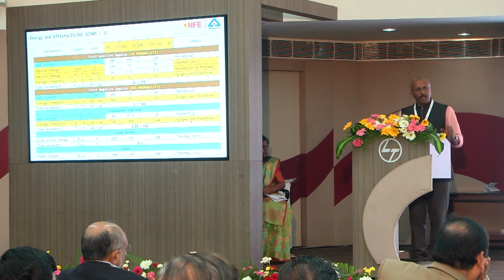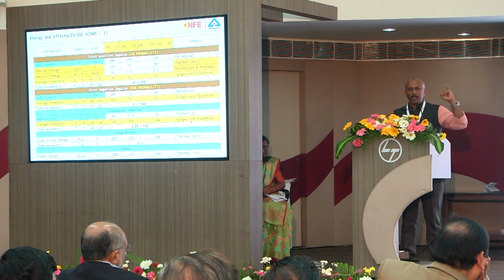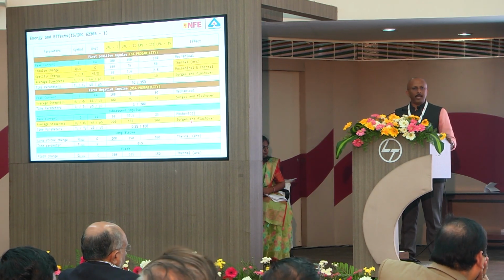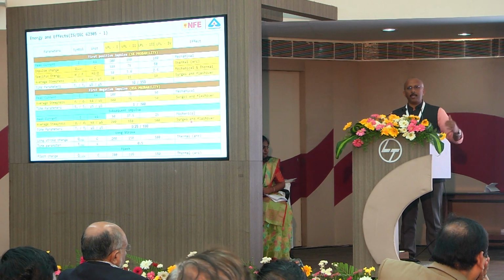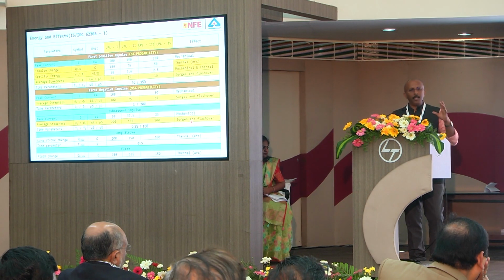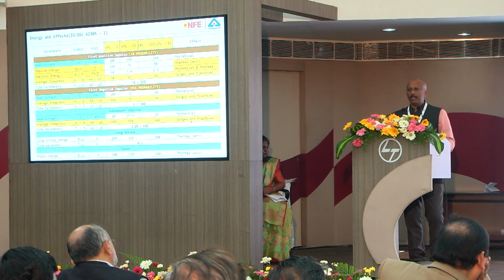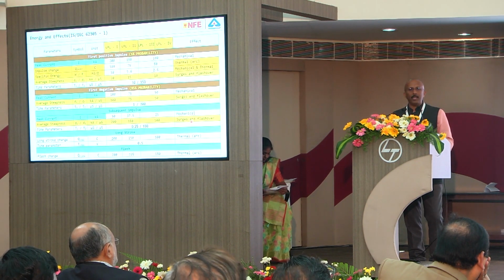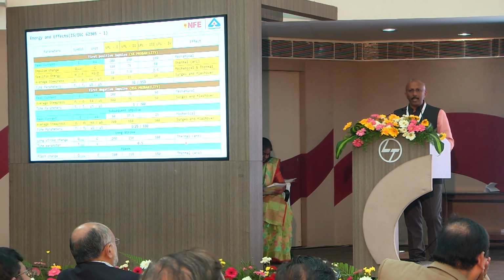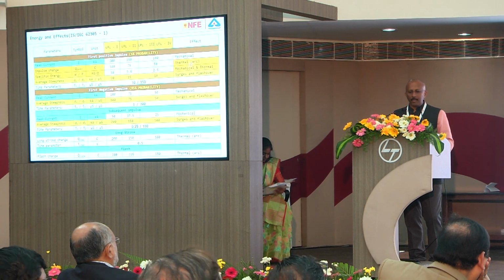So just keep in mind that positive strike, negative strike, then 5% is positive, 95% is negative, then you have the current, the specific energy, the charge, the rate of change of current. All these matter when you design lightning protection in your installation, because the person who is designing has to really look deep into the subject and find out the effect. Finally, our aim is to reduce this effect, mechanical and thermal surges and flash.